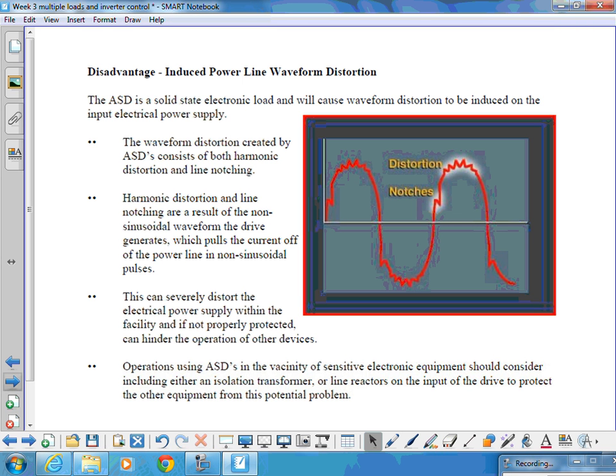Operations using ASDs in the vicinity of sensitive electronic equipment should consider including either an isolation transformer or line reactors on the input of the drive to protect the other equipment from this potential problem, by installing additional equipment to protect other sensitive equipment from the harmonics created by these drives.